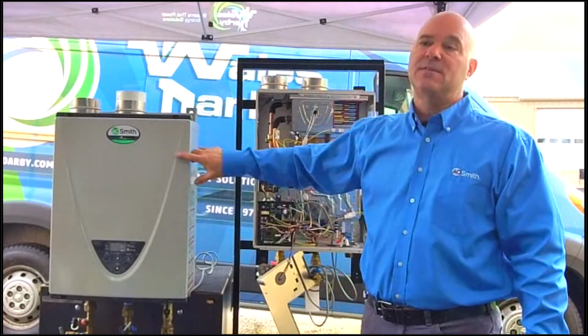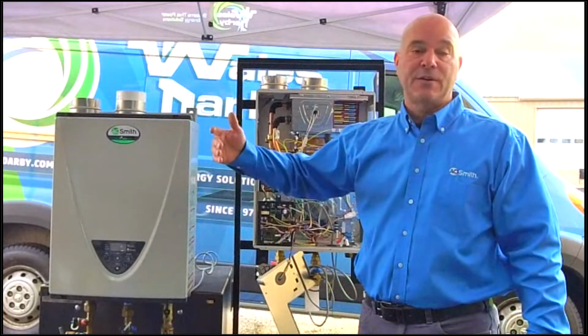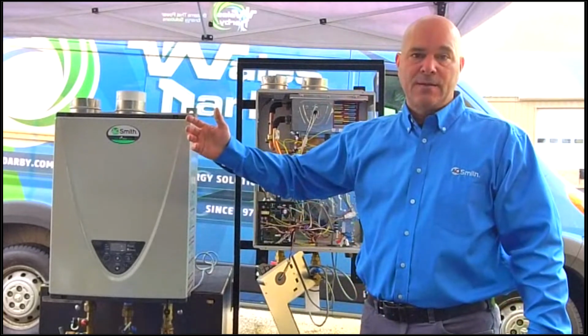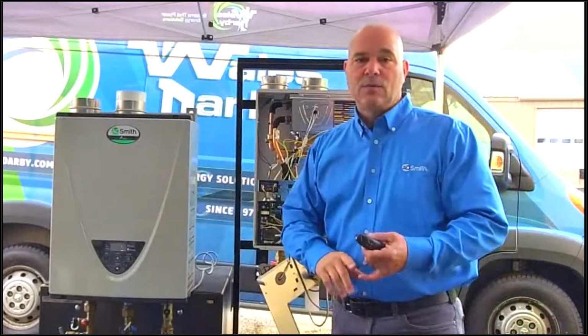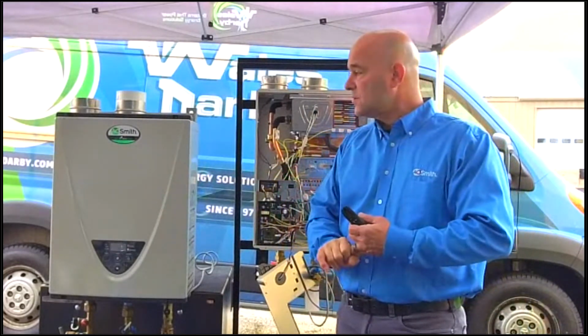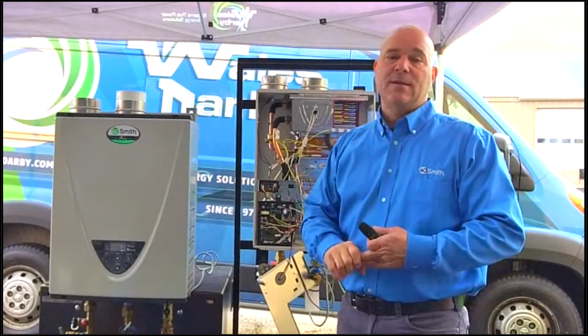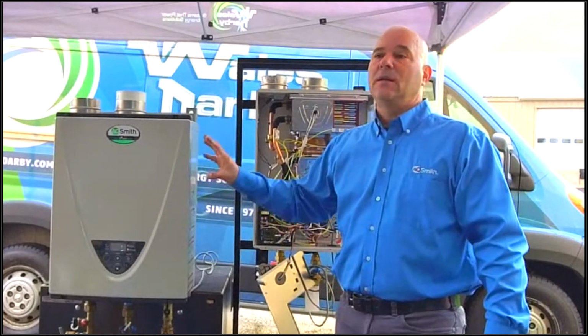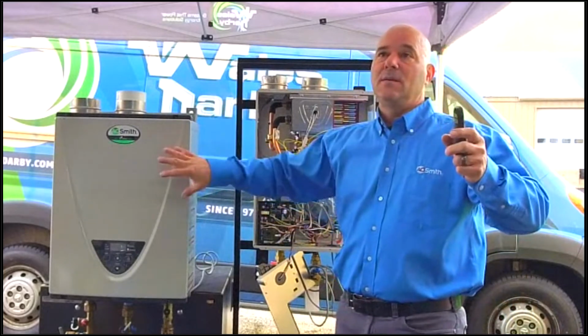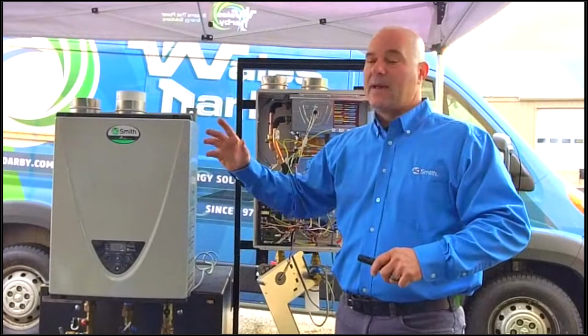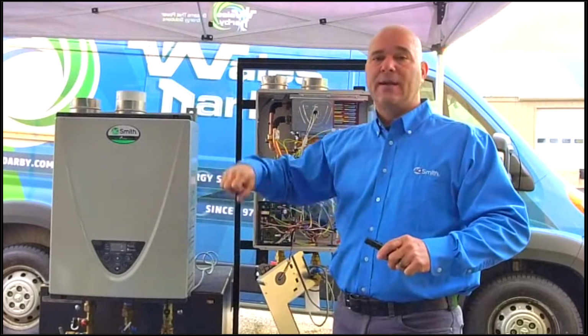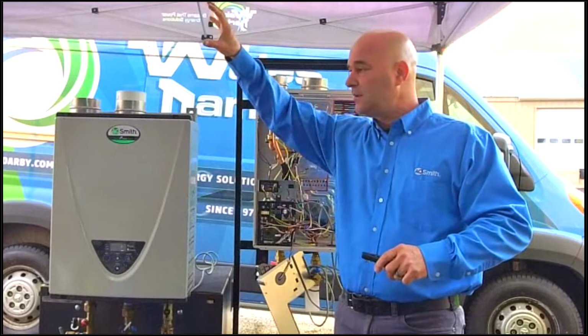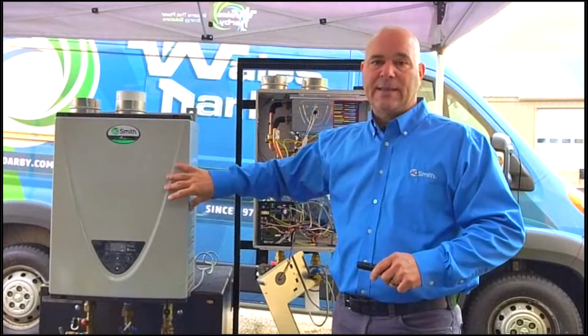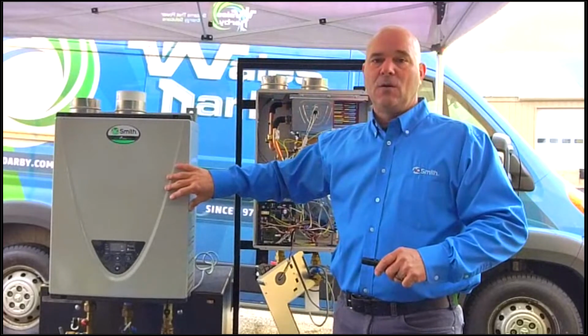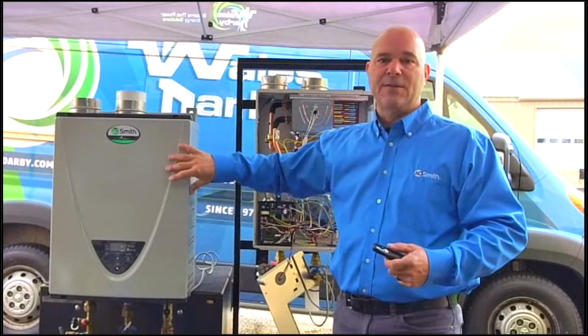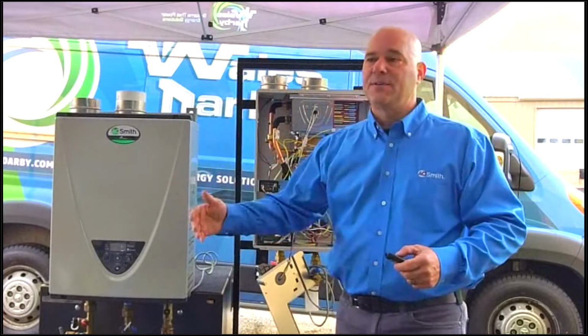We have alternative piping methods where you pipe these primary, secondary, reverse return with storage tanks. Depending on the size of the building, depending on the storage tank, we're doing some hotels. We've done some schools. We've done some condo complexes where we're putting these because a lot of times in these high rises, the mechanicals will be on the roof, and instead of having to rent a crane and shut a street down to carry the new water heaters up onto the roof and put them into the buildings, we can take this and go right up an elevator. So a lot of times this is a good option for those type applications. Just get you thinking outside of the box, outside of the norm.